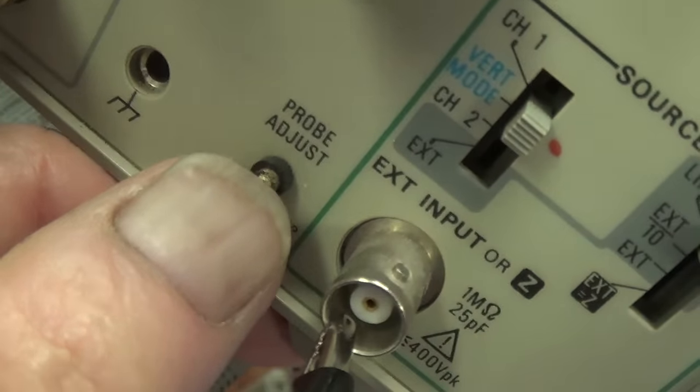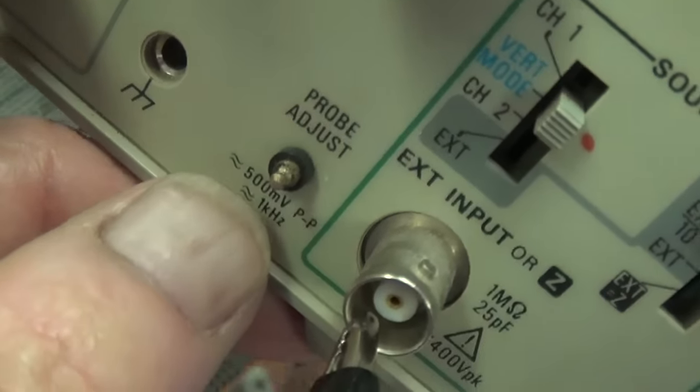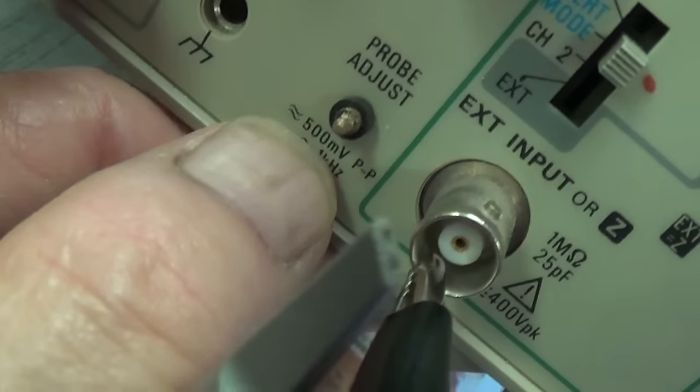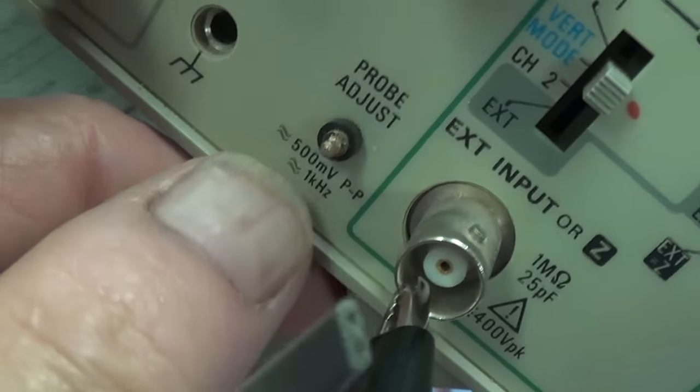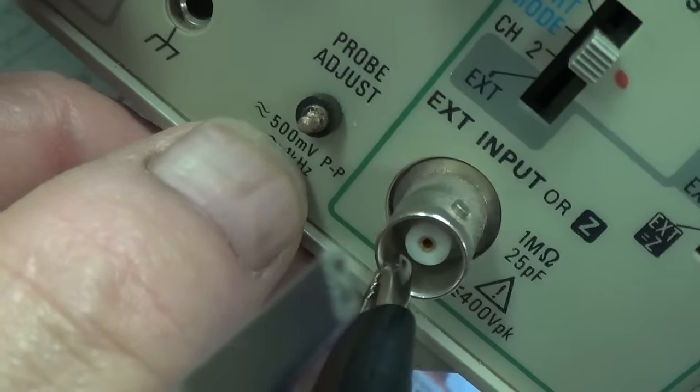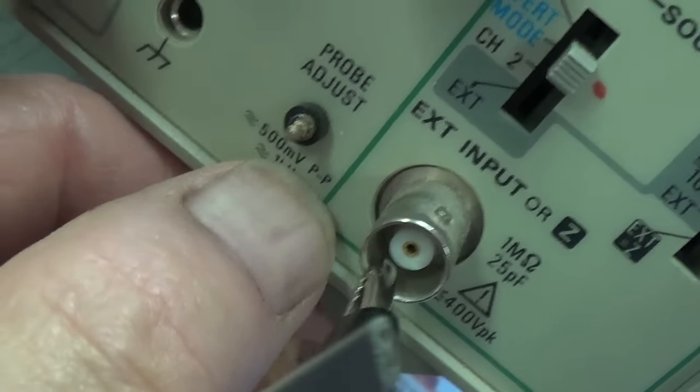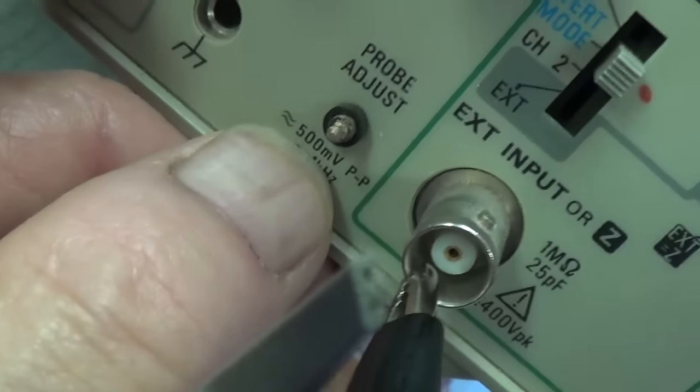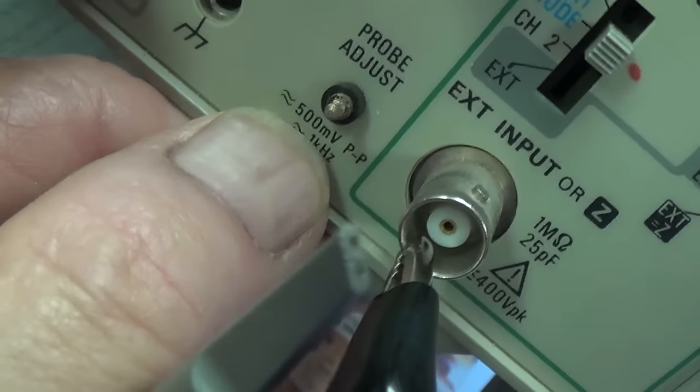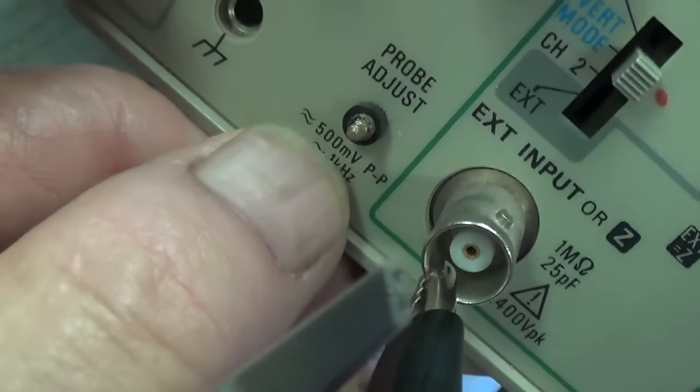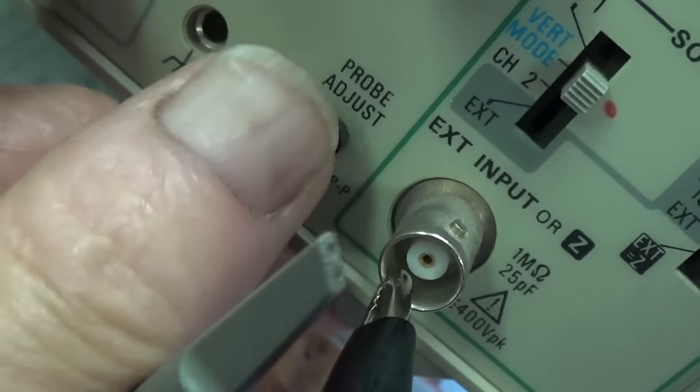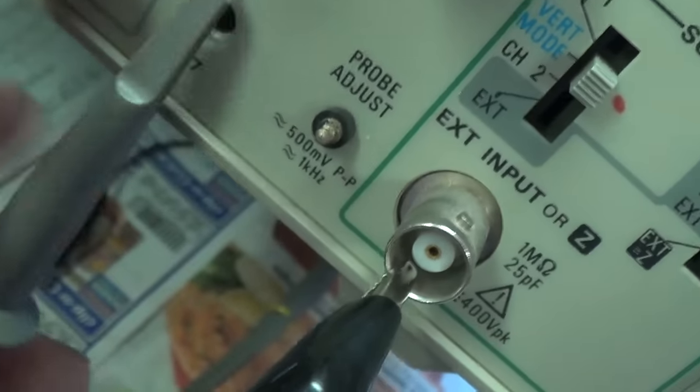Okay, I came over here and I removed my probe from the probe adjust to look at what the heck this is putting out. And it says 500 millivolts. Okay, peak to peak. Well, 500 millivolts is a fancy way of saying what? A half a volt. Okay, so that's what is being put out from my probe adjust. Let me put my probe back on that lug.